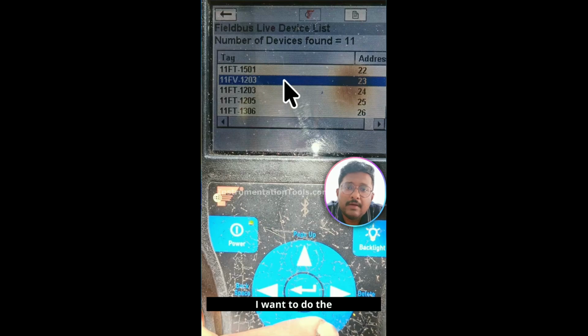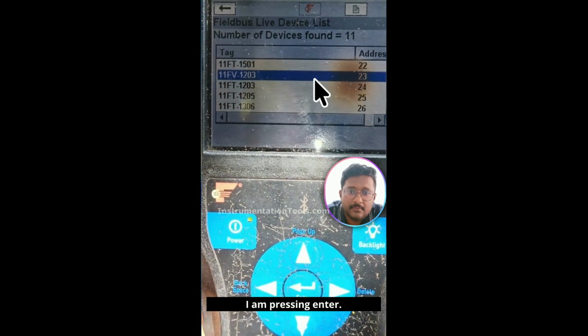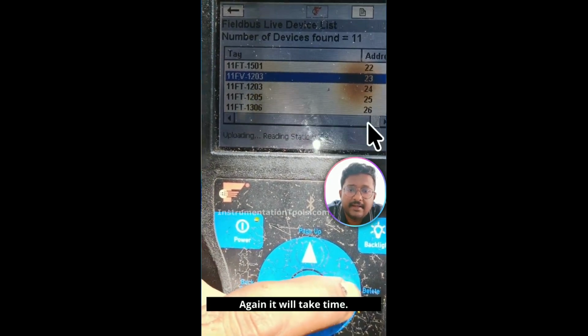For this control valve, I want to do the calibration now. But remember, by connecting your handheld communicator in a segment at any place, at any instrument, you can access all instrument parameters. You can view the diagnostics, you can change the configuration parameters, or you can view the configuration parameters. Okay, you can do anything at any place. Next, I will press enter, and then it will go to the 11FV1203. I'm pressing enter. Again, it will take time.